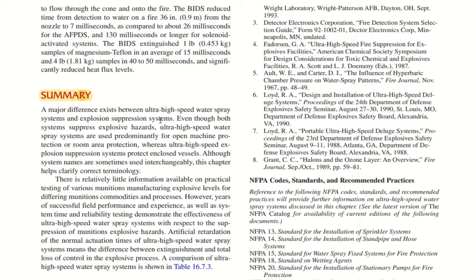Even though both systems suppress explosive hazards, ultra high speed water spray systems are used predominantly for open machine protection or room area protection, whereas ultra high speed explosion suppression systems protect enclosed vessels. Although system names are sometimes used interchangeably, this chapter helps clarify correct terminology.